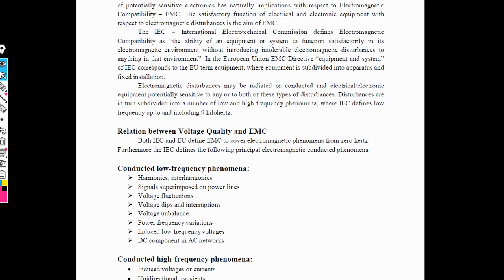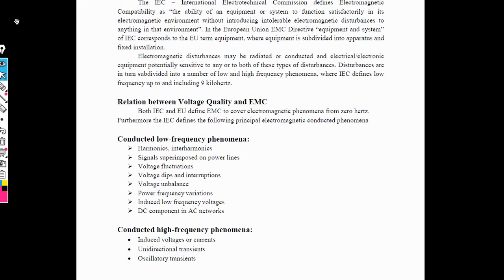Okay, at that instant we need low frequency phenomena. Electromagnetic compatibility defines low frequency and high frequency. First we explain the low frequency phenomena. That means conducted harmonics and interharmonics, then signals of the power line, then voltage fluctuation, then voltage dips and voltage interruption, then voltage unbalance, then power frequency variation, that is low, medium and high, then low frequency voltage, then DC component in the AC network. Also we need a DC filter and AC filter to minimize the losses in the network. Okay, this is the phenomena of low frequency.